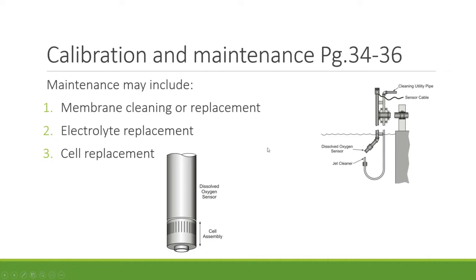Maintenance includes membrane cleaning or replacement and electrolyte replacement, though in modern practice the standard operating procedure is typically to replace the entire cell rather than refill it. Some cells have replaceable electrolyte; others are simply replaced as a unit. The state of the art today tends toward replaceable cell assemblies.